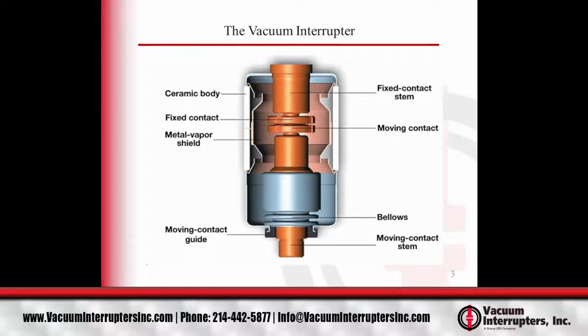The materials, the stainless steels, the coppers, everything that is internal to the vacuum interrupter has some gas content inside. Over the life of the vacuum interrupter, these gases will migrate out, being in a vacuum. Also, you have very small molecules like hydrogen and possibly helium that can leak through the materials and small pathways connecting all the parts together. So eventually, all vacuum interrupters fail. Some fail much sooner than others. It's all dependent on the quality of the materials that it's made of and its duty.